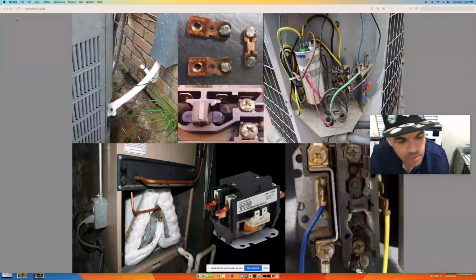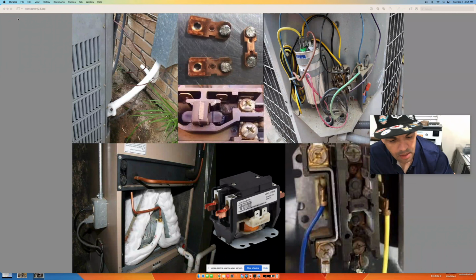Okay, in this video, we're going to be talking about your contactor and what happens to your AC system when your contactors go bad. Okay, a contactor is a fancy word for just your main switch. It's pretty much a switch, but they call it a contactor. And what happens is every time your thermostat calls for cooling, your thermostat is going to send a low voltage signal to your contactor outside, or that main switch.